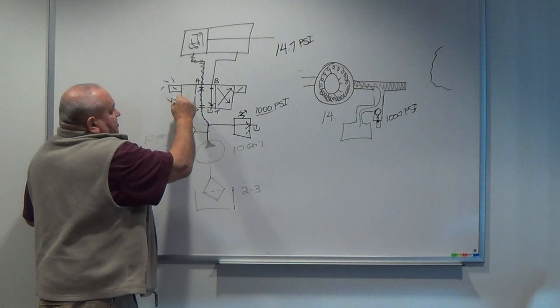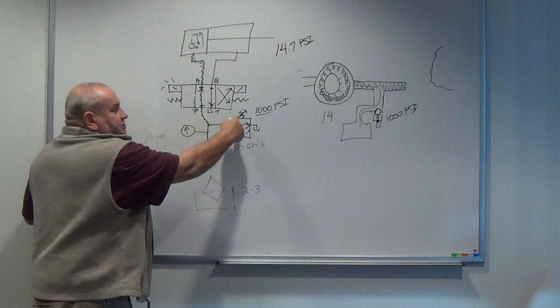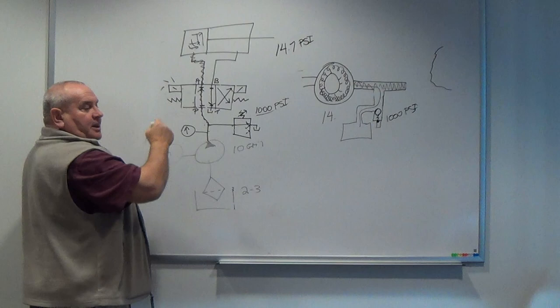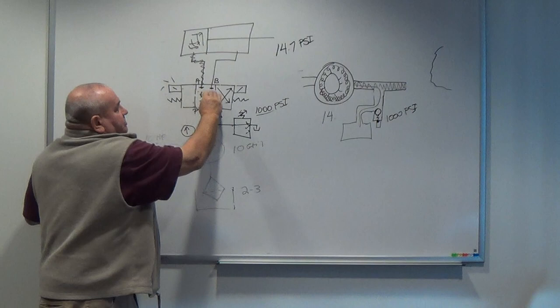Now when we look at this valve, I've got a little squiggly line here and I've got a little squiggly line over here. Those are springs. So when I deactivate this solenoid so I don't bring any more electricity into it, what is this spring going to do? It closes the center again. Sure. It's going to take this unit here and it's now going to push it back over here.